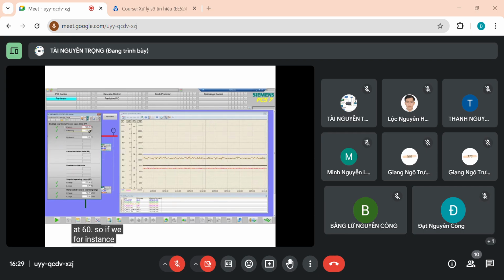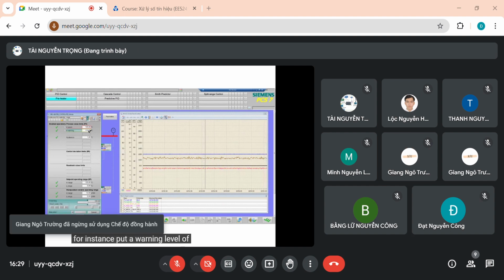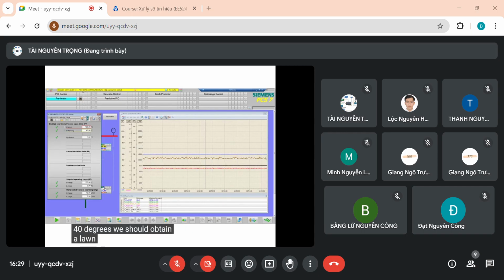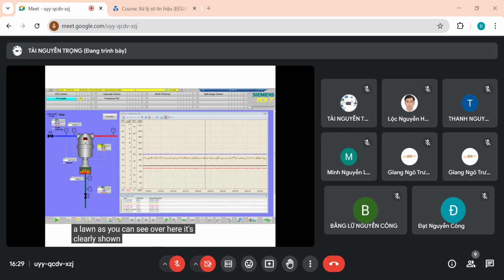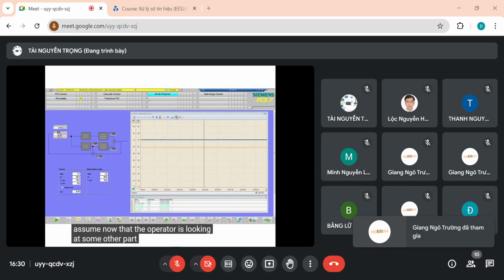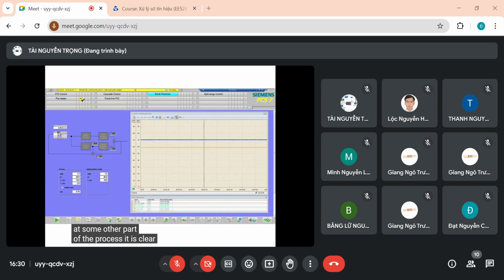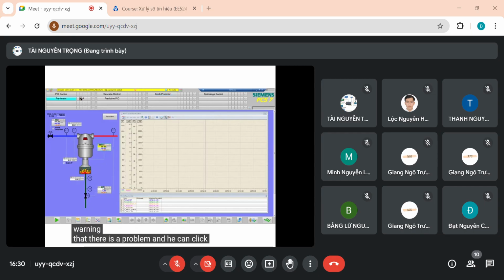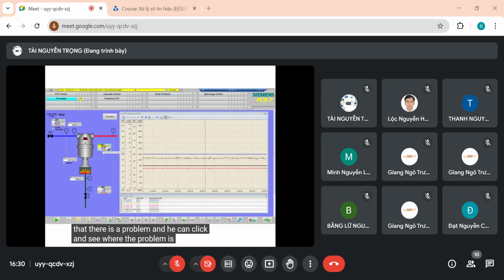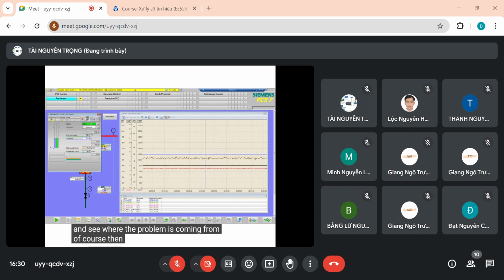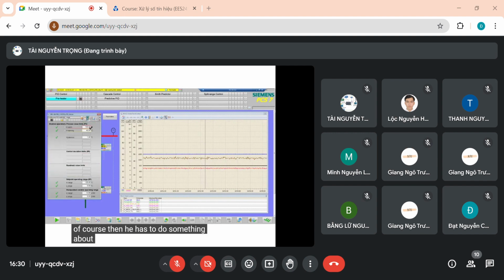So if we, for instance, put a warning level of 40 degrees, we should obtain an alarm. As you can see over here, it's clearly shown that the PV of this controller has exceeded the warning limit. Assume now that the operator is looking at some other part of the process. It is clear from this warning that there is a problem, and he can click and see where the problem is coming from. Of course, then he has to do something about this problem.